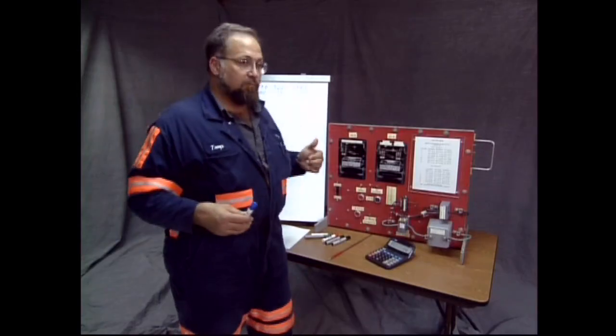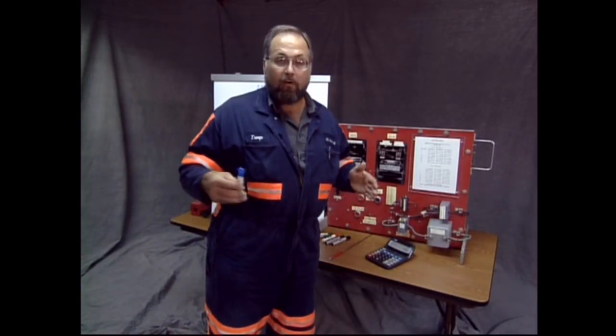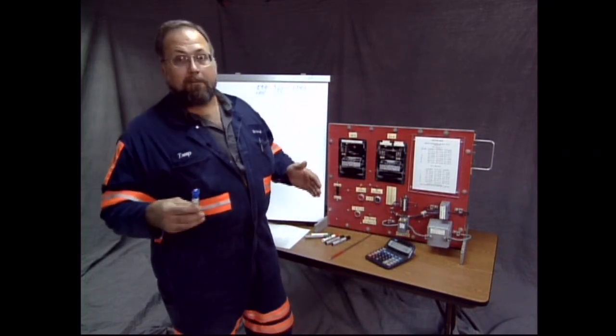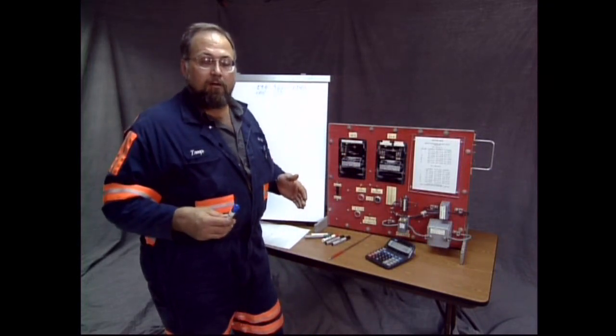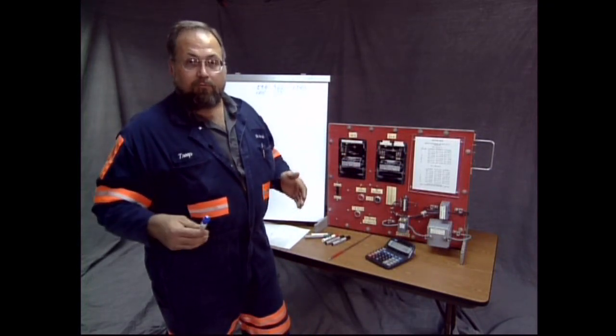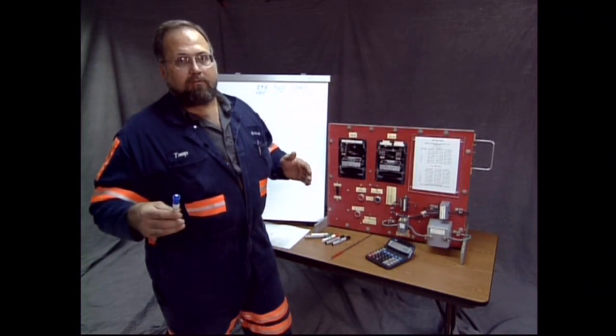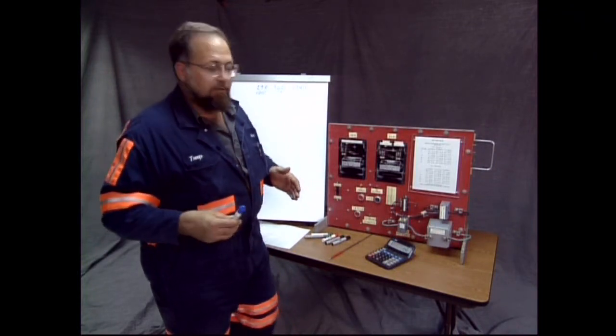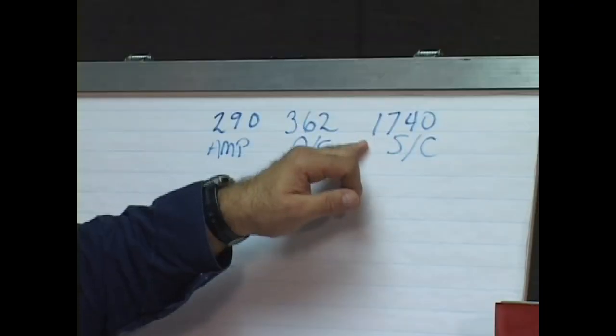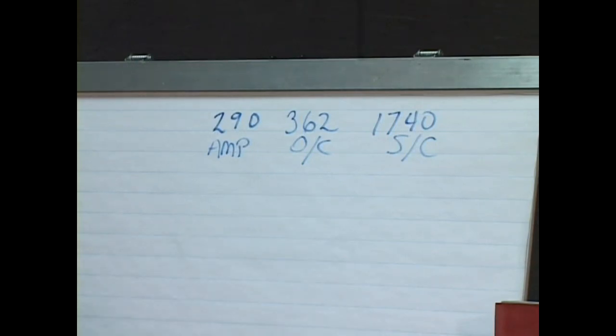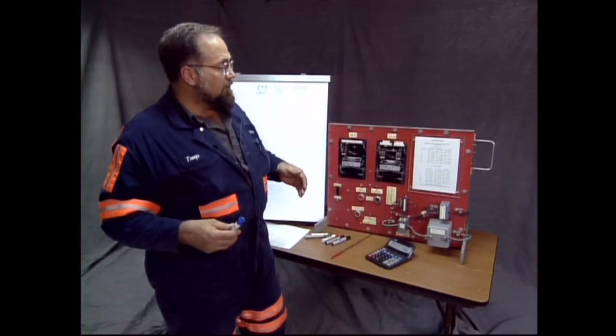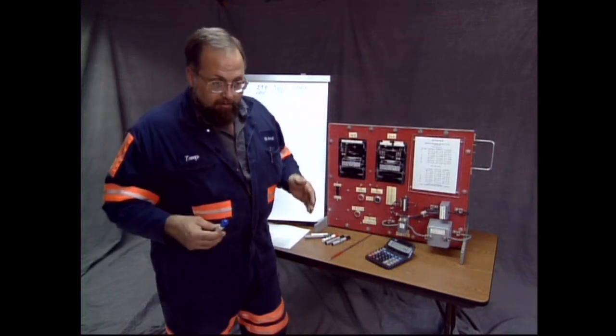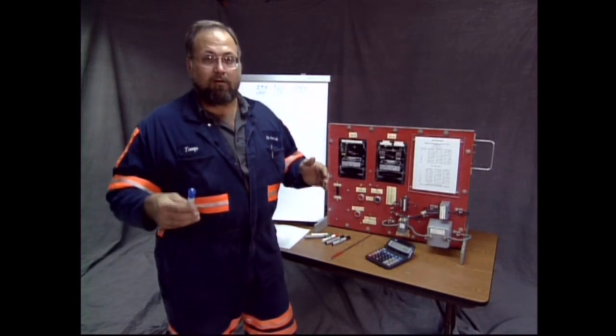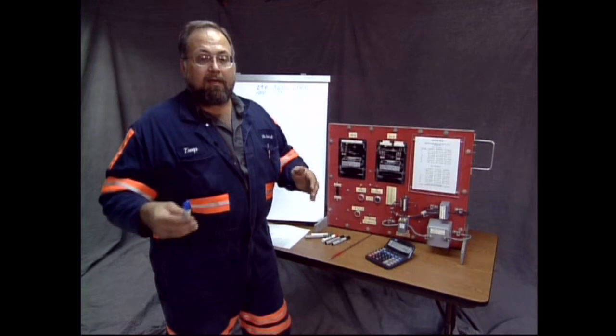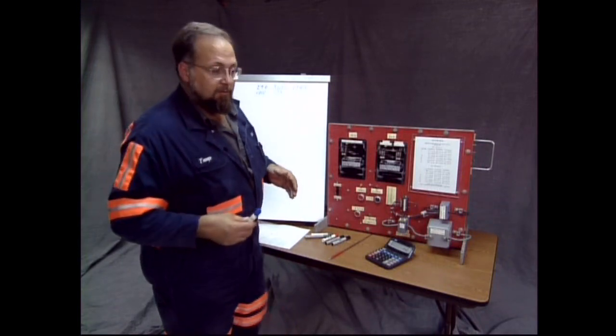Short circuit, that's more or less fire insurance. Now, you don't have a house fire every month. You want to be protected. If you do have a house fire, you want to be covered for that, but you don't have a house fire every month. That's short circuit. So we're going to set at maximum levels, maximum available to us on this panel here, but in real life, you don't want to push the envelope. You want to be adequate, but not excessive.